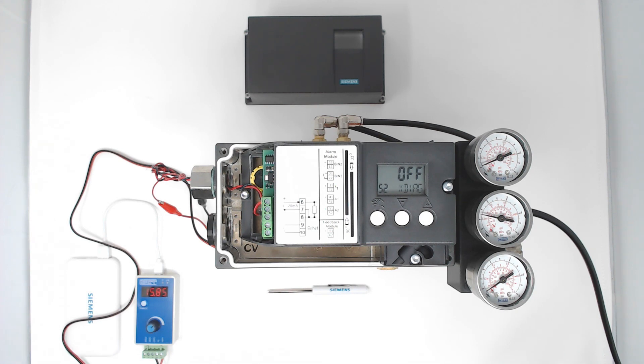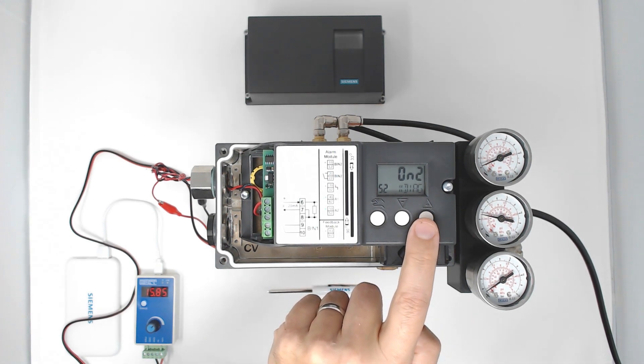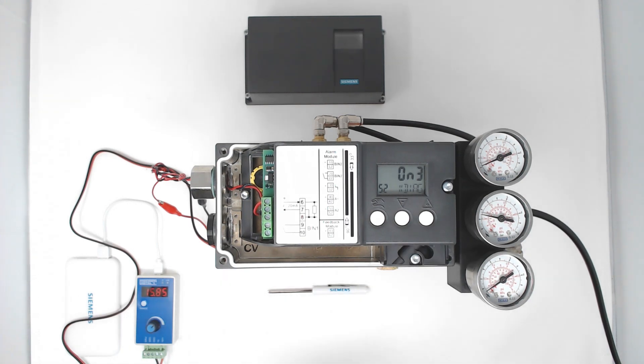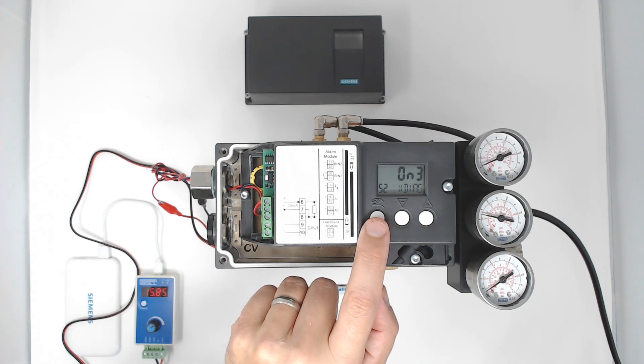By default this parameter is turned off. You have on one which provides one threshold per diagnostic, on two is two thresholds, and on three is three thresholds per diagnostic. Think of them as green, yellow, and red warning lights.